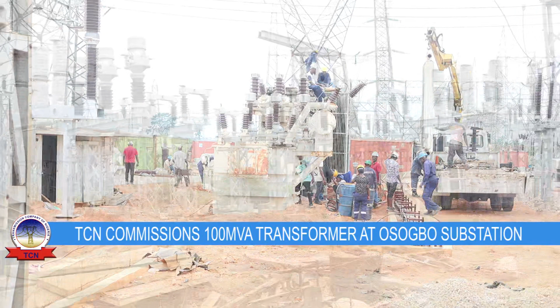He said TCN is thinking well ahead of the people's demand, matching future needs of the state. By the time the 100 MVA transformer project is complete, it will provide four 33 kV radial feeders, an additional corridor for more load to be distributed into the town and the designated industrial area, with bays waiting for industries to evacuate energy to meet their immediate demand.